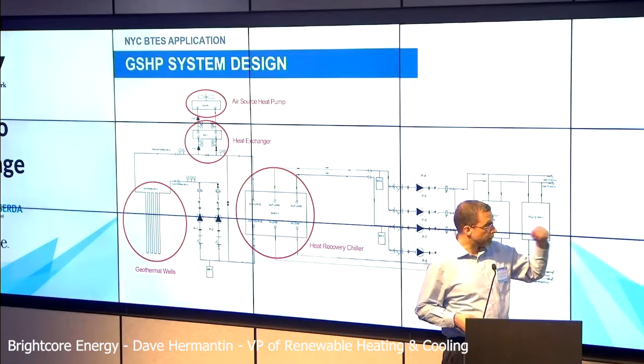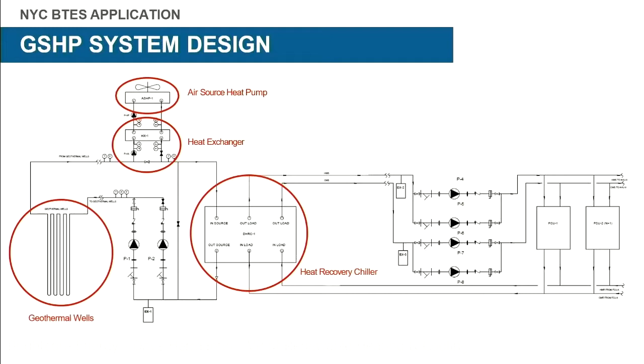What's different is what's on the load side, on the left-hand side. On the left-hand side, you'll see geothermal wells circled in the lower left-hand corner of this, and an air source heat pump on the upper side of the graphic. The way the system is designed to work is that it's going to operate as a standard ground source system for the majority of the year. But during peak cooling conditions, it helps serve this cooling dominant area by storing up or preconditioning the loops during overnight periods. And we're modeling an 18% reduction in energy during peak cooling.